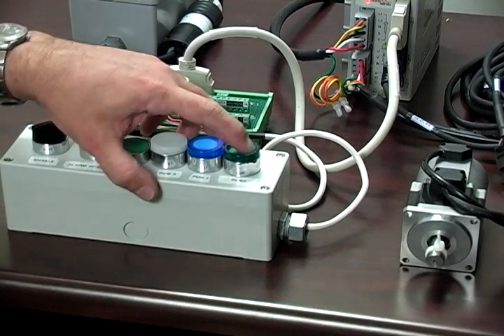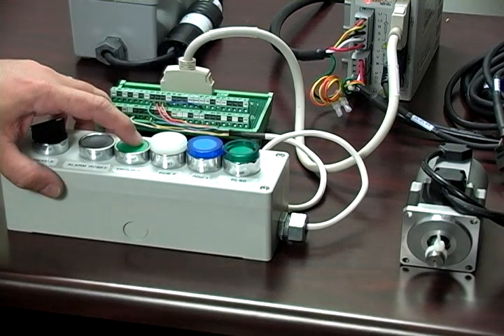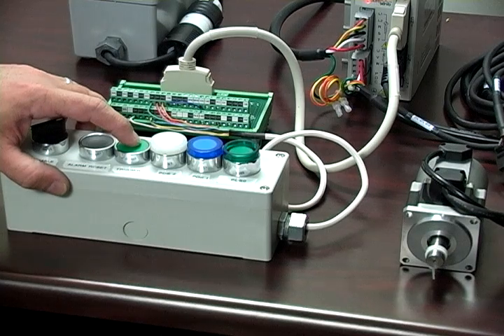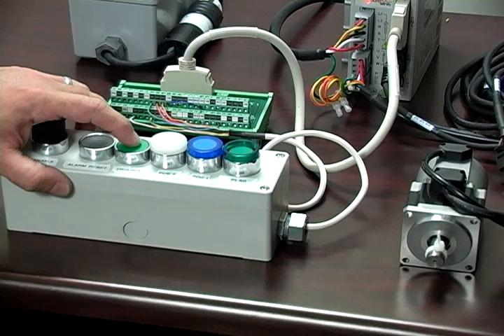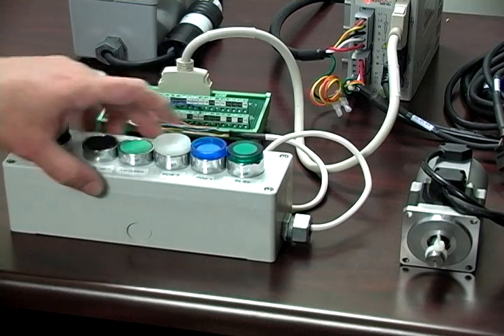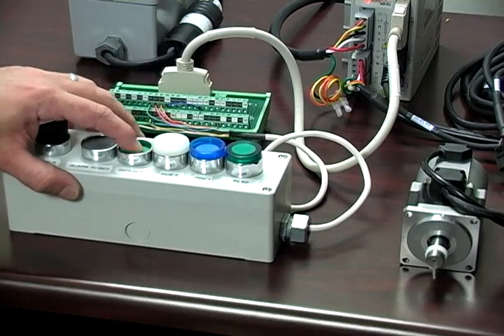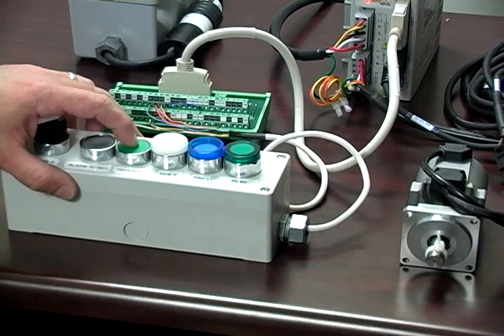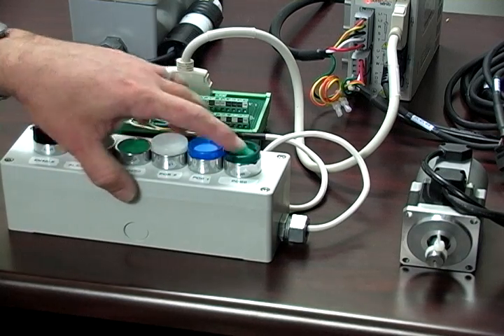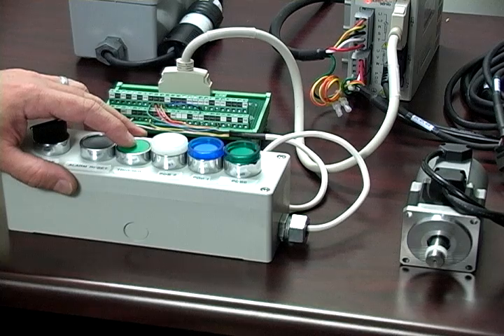If I toggle the POS 0 input to select position 2 and hit the trigger again, the shaft rotates three and a half turns exactly. Selecting position 3 yields one quarter turns per trigger. Position 4 generates the 25.4 turns that we programmed and selecting position 5 results in a long 100 revolution move.